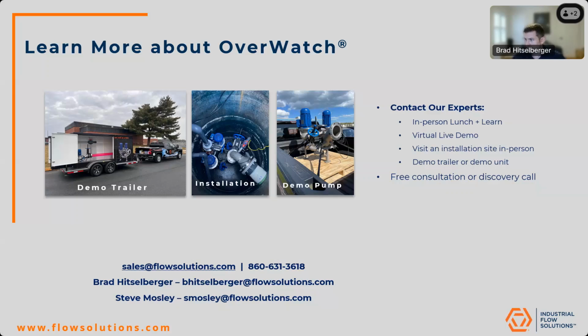Great, thank you. And then how much room do you need for an average installation? So for our typical installations, we have a minimum installation sheet that we supply that shows all the valves plumbed up and how it would align. And it's about 6 feet in diameter. I've seen them go in about 48-inch basins for some of the smaller ones we do as well. So it all depends on the size, but the most popular body size we do, for about 40 or 50 horsepower and down, will fit in a 6-foot basin.